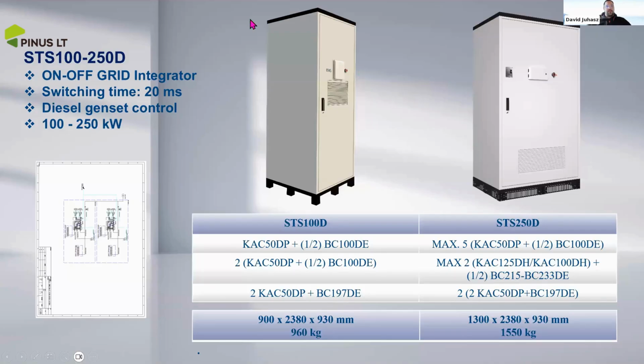This is the STS, how it looks like. It's a standard cabinet with air condition and electronic device inside. It has the genset control and the standalone EMS included inside the door. And in case of usage of this, the other EMS in each cabinet will be the slaves, and this one will be the master. And from the cloud we can operate this EMS remotely.